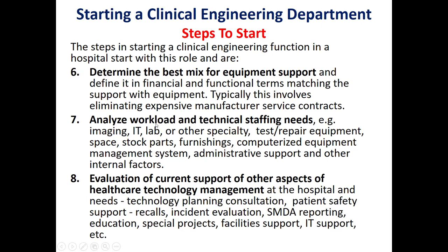After that, we will make an analysis of the workload and technical staffing needs — for example, whether we need a team specialized in laboratory equipment, imaging, or other specialties. We also consider what type of testing and repair equipment is needed, what space is required, what spare parts should be in stock, furnishings, and what type of computerized management system we should use to manage medical devices in the hospital.